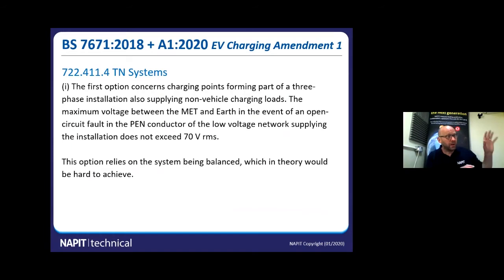You're going to know where the different loads are. You're going to be able to balance them up. You're going to be able to get the phases fairly balanced. But in theory, as the installation goes on, loads change, different circuits get moved around, and the phases become unbalanced. Then you get situations where single phase loads kick in and out, causing imbalance in the system, and therefore current flowing in the neutral. This is what can cause the voltage to rise above 70 volts if we have a lost PEN conductor. So it's quite hard to achieve, but in theory it can be met.